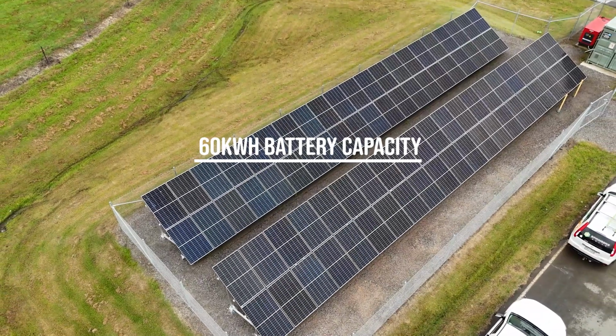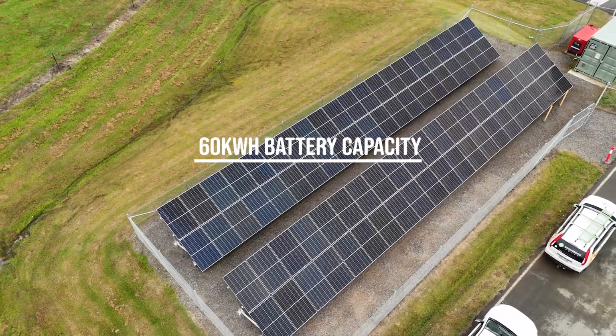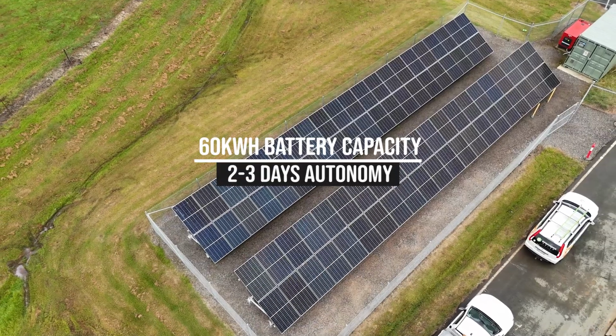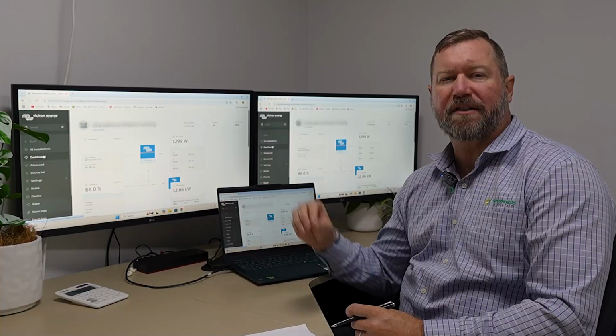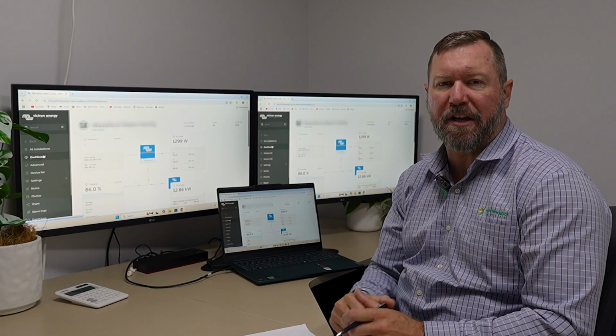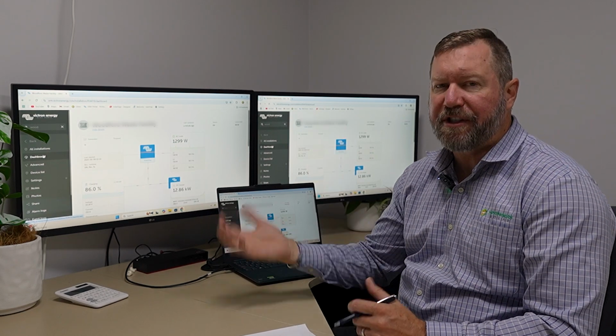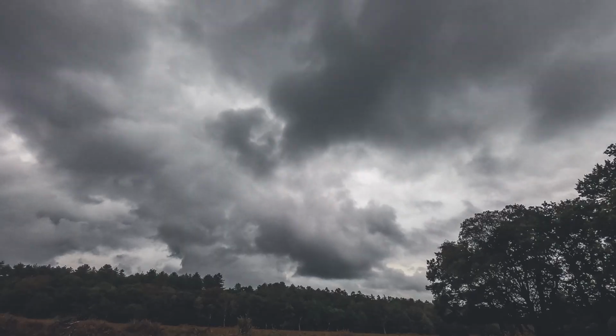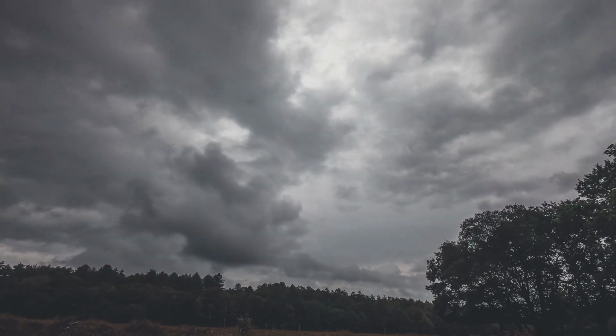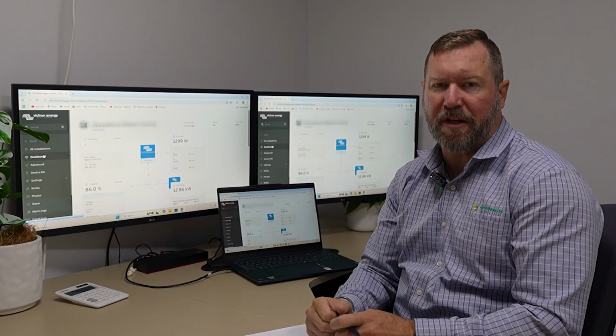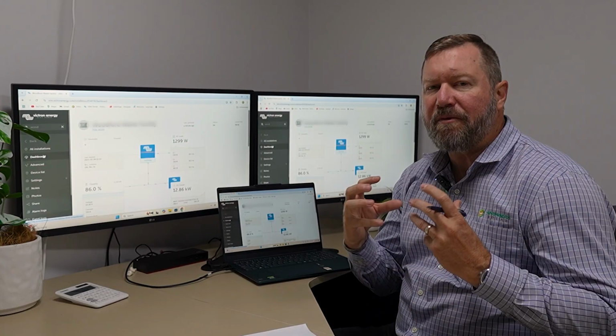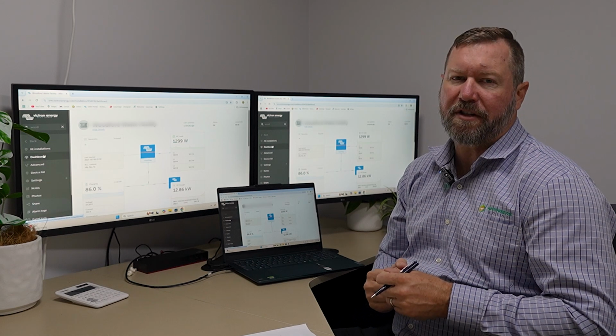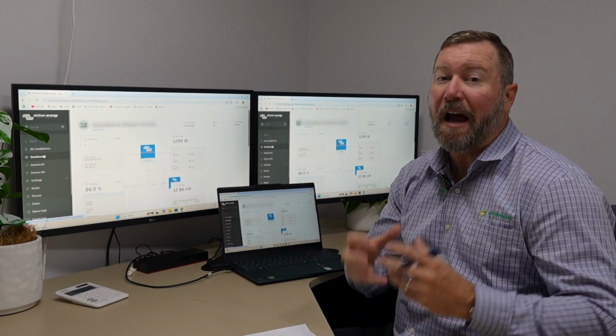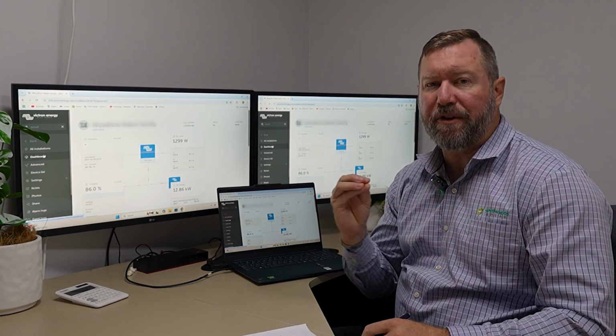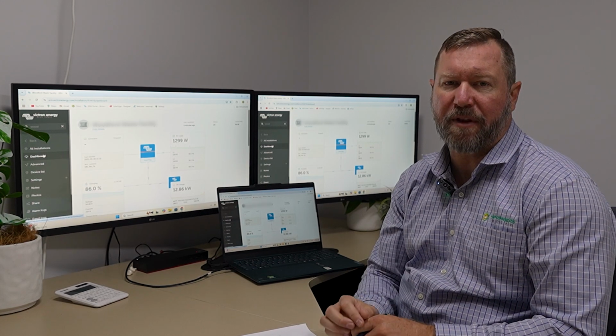Now, this system being a 60 kilowatt hour total capacity battery system, it's good for about 2 or 3 days autonomy. So what that means is the site uses between 20 and 30 kilowatt hours a day, and we've got 60 kilowatt hours of energy storage. So even if the sun did not shine, the system will run for 3 days before needing to call up the generator. This is a robust, well-engineered solar system and a well-engineered electrical system to ensure that this site never goes down and is never without power.